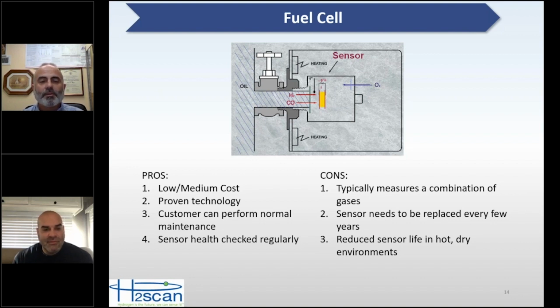So the pros for this technology, it is a low to medium cost unit, depending on which one you choose. It's proven technology. It's been around a very long time, probably about 30 years, I'm guessing. The sensors do have to be replaced periodically. So the nice thing is customers can do that maintenance on their own. And most of the sensors that I'm aware of, the fuel cells, they do a regular health check. And so depending on whose you buy, I believe most of them will tell you when the sensor is bad and needs to be replaced.